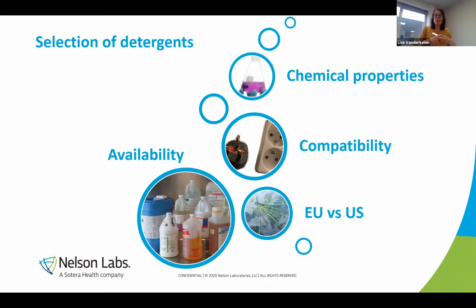Another thing is that you should look at the availability of the detergent on the market on which you want to put your device. So if, for instance, in Europe, we don't have access to detergents and it's only available in the US, it is not a good cleaning validation and it will not give you a stamp on your passport for the European market. So sometimes it's necessary to use two different types of detergents to enter both markets. Okay, so think about the detergent, but it should be available and compatible at least with your device.